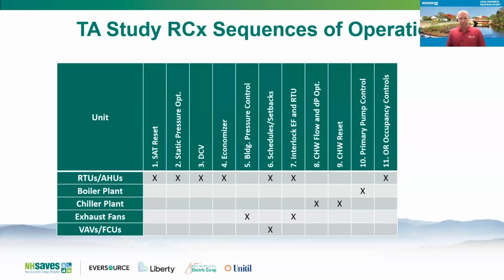And then one of my favorites from this one was the OR occupancy controls. So ORs have to maintain a certain air changes per hour and dew point control when the ORs are being used. It's really critical space. Except when they're not occupied, they don't need to maintain those same air changes per hour and temperature and humidity requirements. So this customer, the facilities manager here was really aggressive and was able to put in occupancy controls so that when those ORs are not being used, and there's nobody in the space, they set them back from an air changes and a dew point control standpoint, and it really can save a lot of energy.